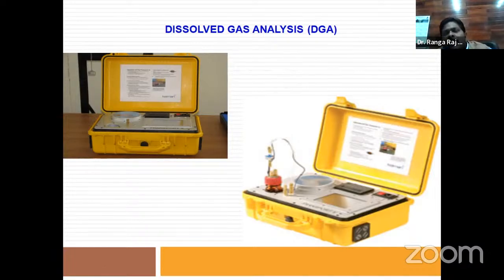That is the way of collecting the sample from the transformer: we insert a test cell into the transformer outlet valve and take the oil out, much like a medical treatment we observe in hospitals and labs. We keep the oil sample in this red bottle and raise its temperature inside a heat chamber. Once the oil temperature rises, we find the generation of gases.